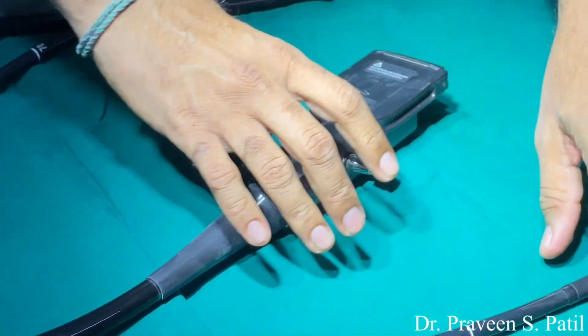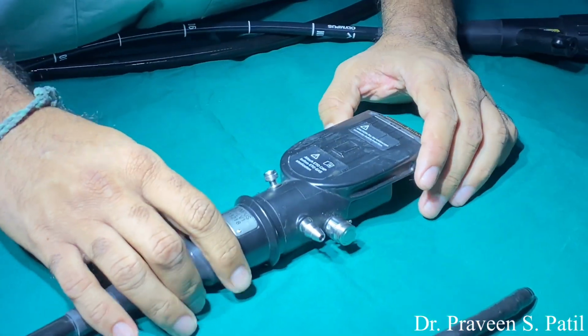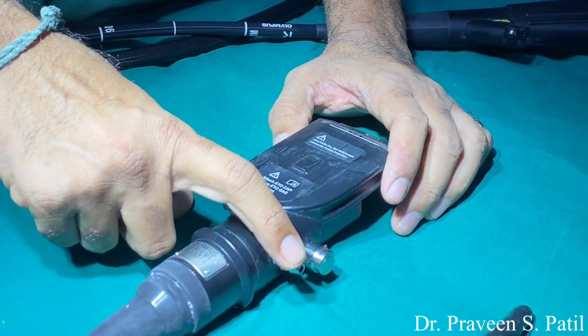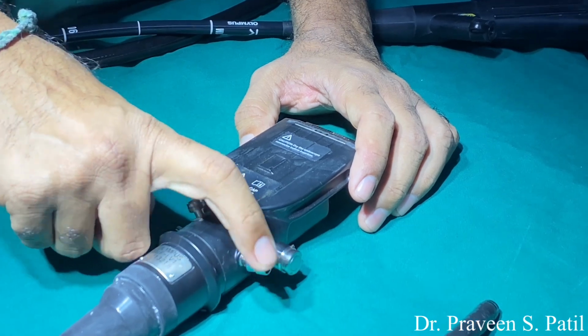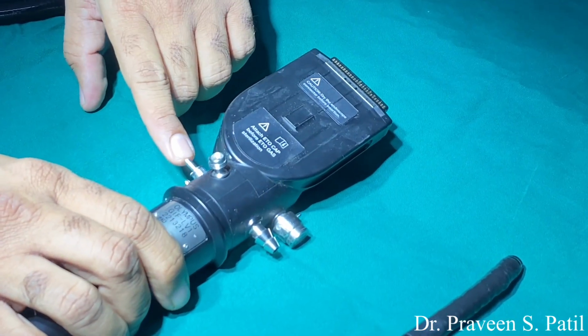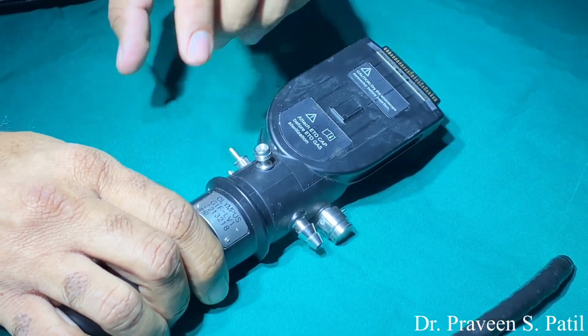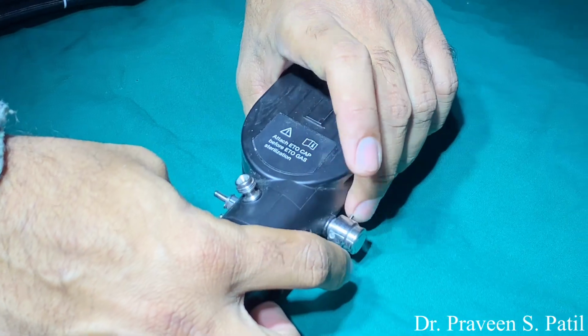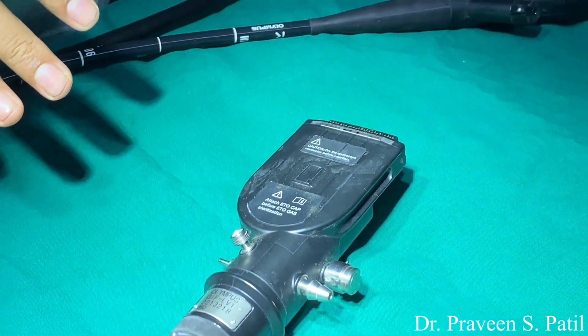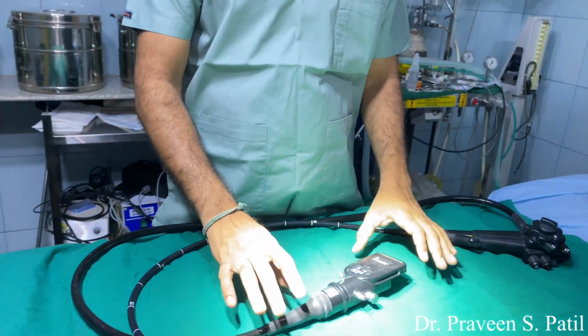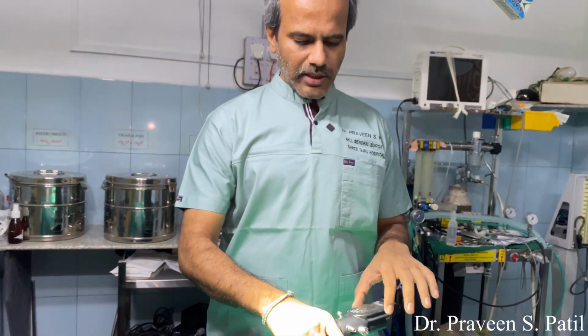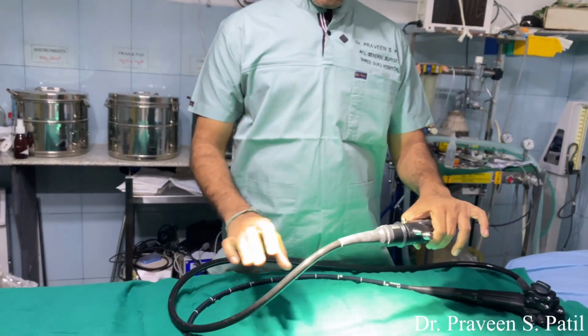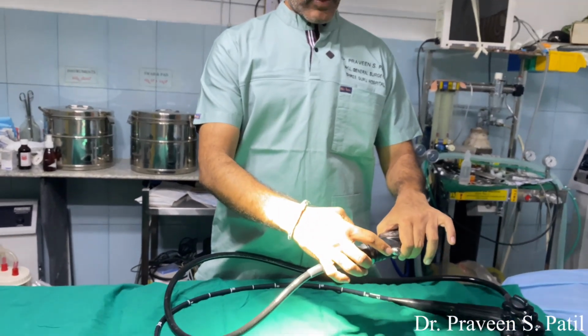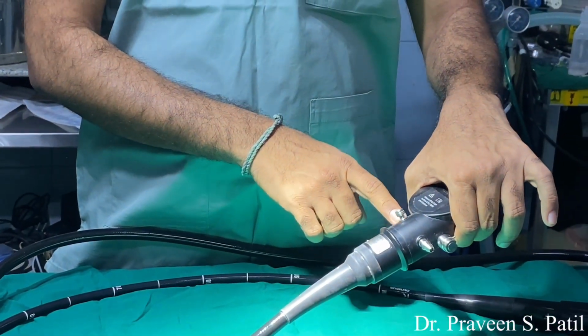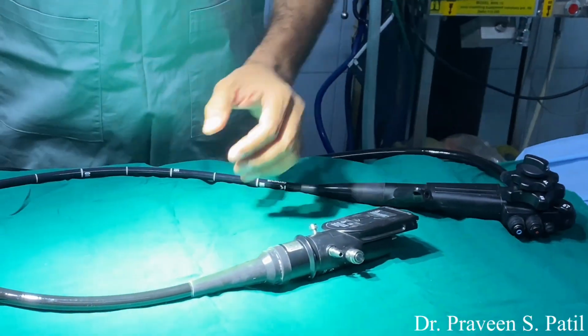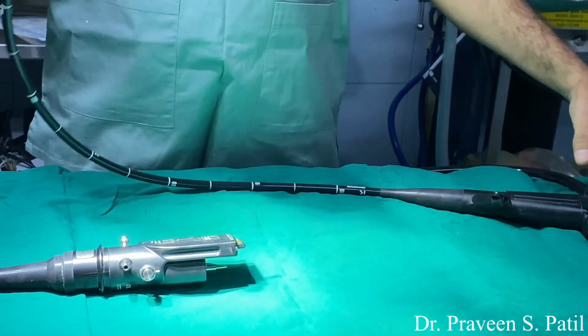And coming to the umbilical cord, we have two openings on either side. This has to be attached to the suction instrument, and this is for the air and water jet. This is for the suctioning. So this is the anatomy of this upper GI endoscope. This end has to be attached to the mother machine, and here we attach the suction tip, the water and air jet, and afterwards it's ready to use. Once the machine is switched on, it is ready to use.